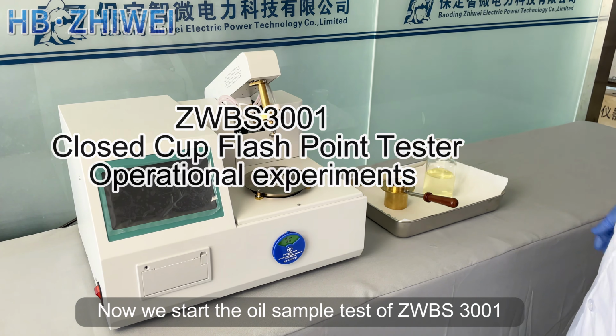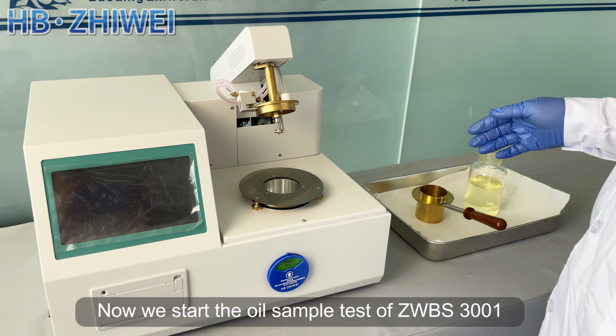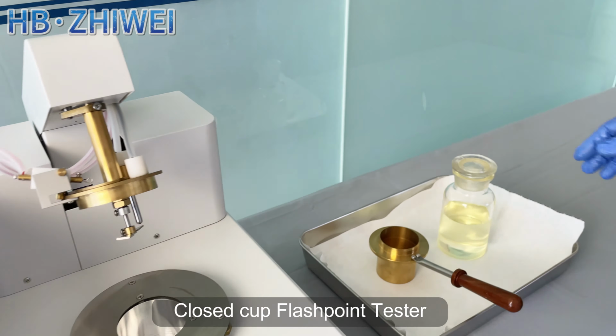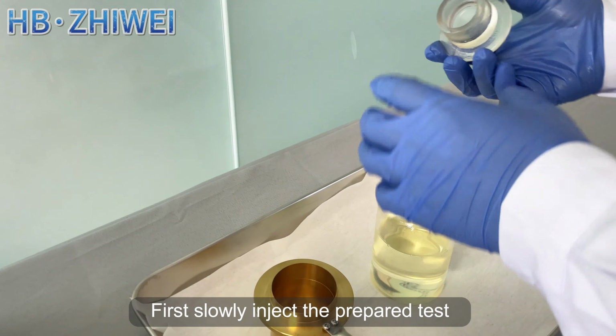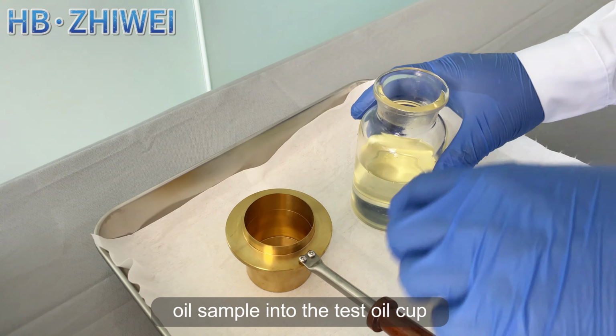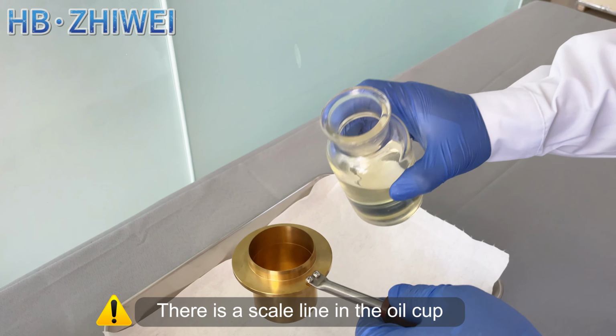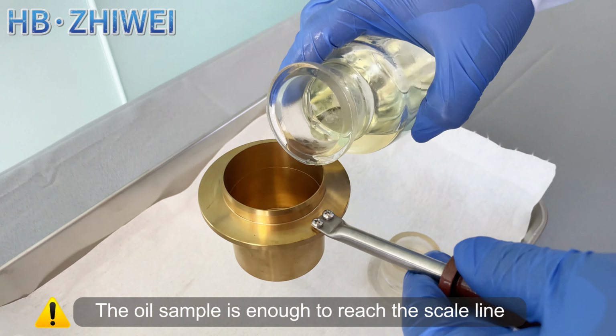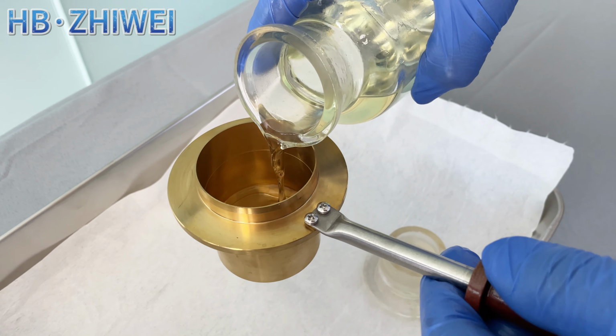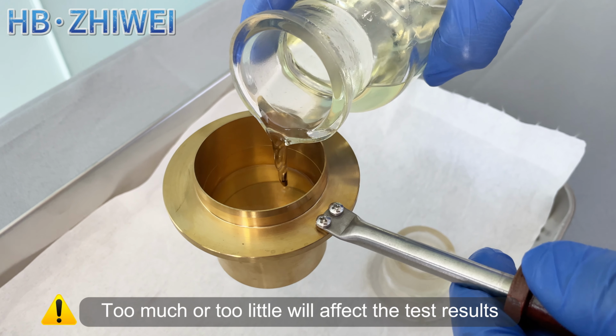Now we start the oil sample test of ZWBS3001, closed cup flashpoint tester. First, slowly inject the prepared test oil sample into the test oil cup. There is a scale line in the oil cup. The oil sample is enough to reach the scale line. Too much or too little will affect the test results.